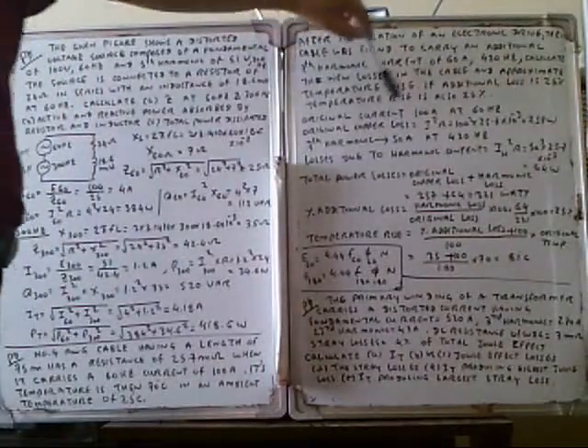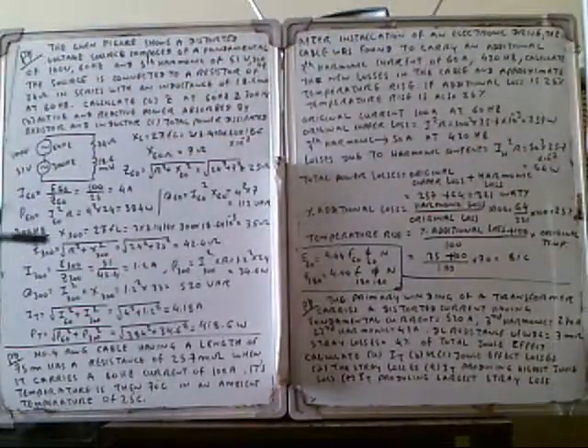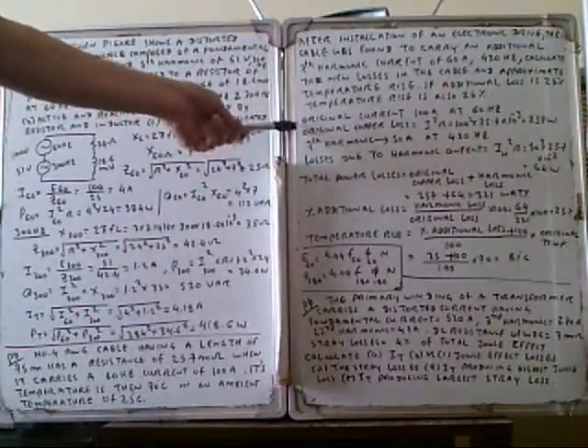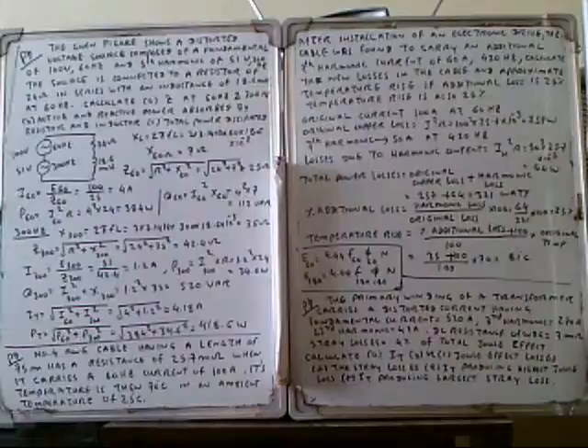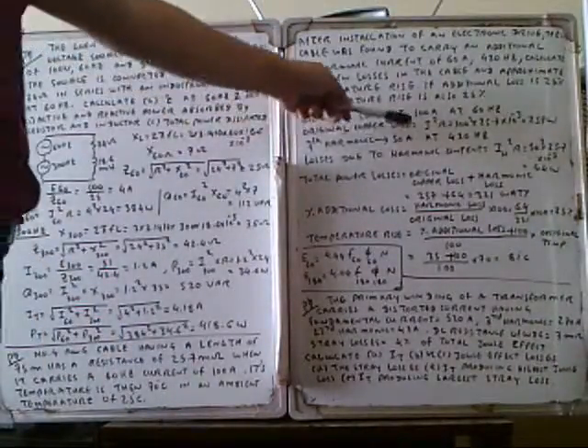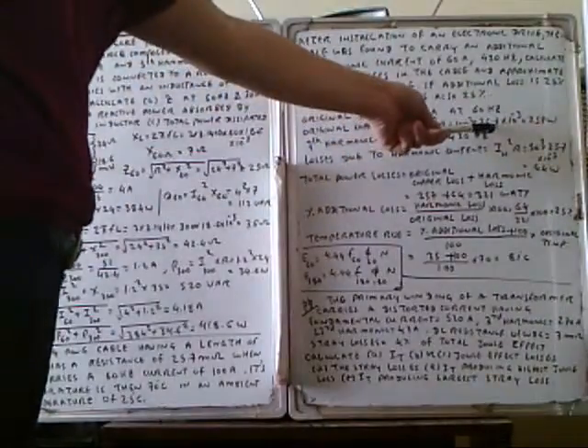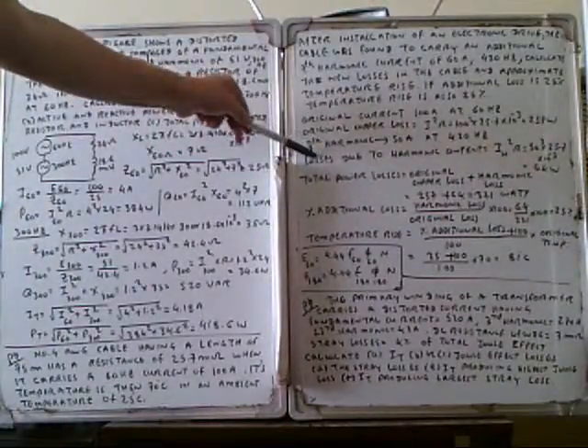Approach based on temperature rise: if the additional loss is 25%, the temperature rise is also 25%. The first reason for this problem given - the original current is 100 amps at 60 Hz. We have to calculate the original copper loss. The 100 amps flows into the resistance value of 25.7 milliohms. Original copper loss is I squared times R. Current squared times resistance of 25.7 times 10^-3 equals 257 watts.